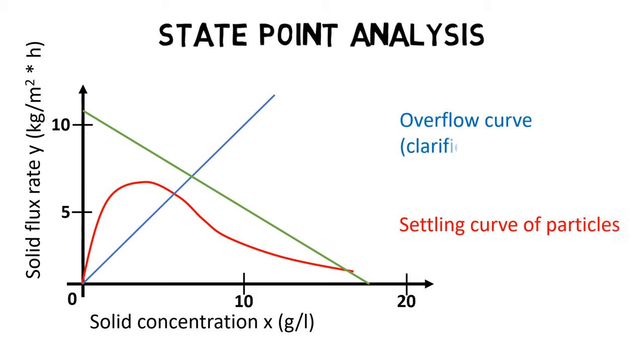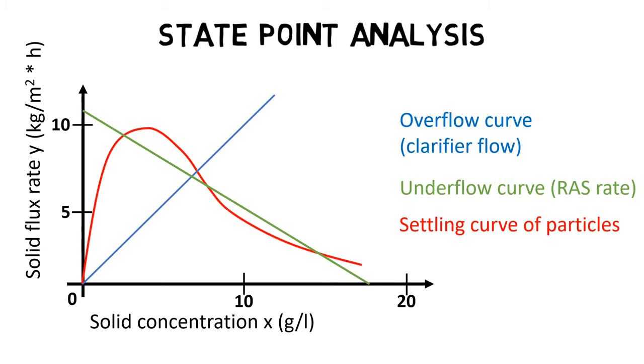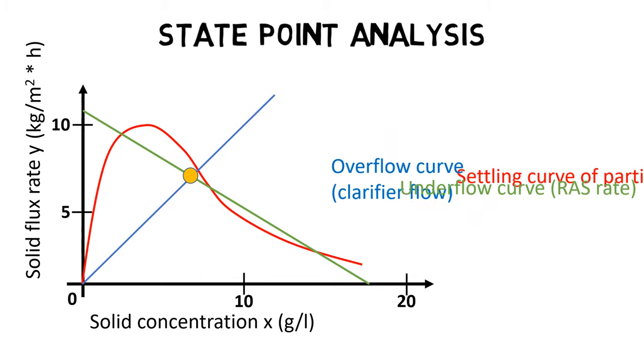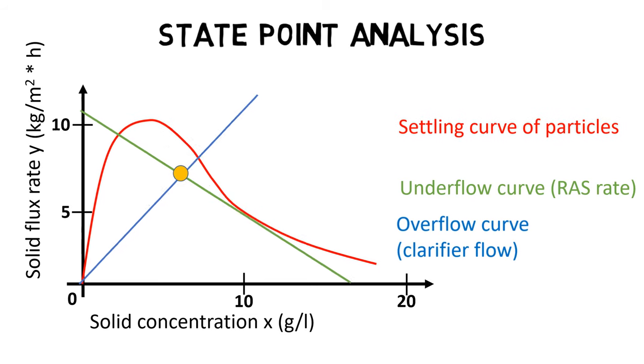the overflow curve to represent the flow through the clarifier, and the underflow curve to represent the RAS rate in the clarifier. The goal is to have the intersection of the overflow and underflow curve underneath the settling curve to allow enough time for solid settling.